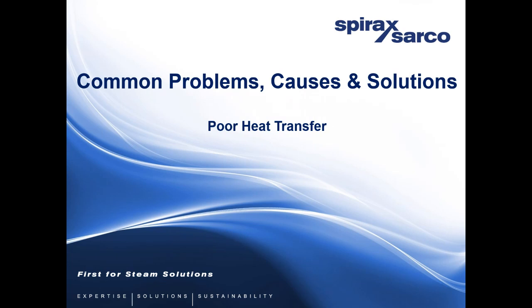Simplest is the sight glass. A sight glass will never fail, not unless the glass cracks, but they're pretty robust. It's the simplest and the quickest way to tell if your trap is failing. And then, depending on your solution, depending on the visibility of your steam traps, because these may be 5-6 meters in the air, there are increasingly costly systems to be able to check. Anything you want to add there, Anthony?